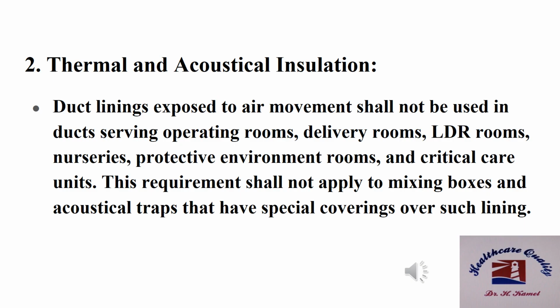Duct linings exposed to air movement shall not be used in ducts serving operating rooms, delivery rooms, LDR rooms, nurseries, protective environment rooms, and critical care units. This requirement shall not apply to mixing boxes and acoustical traps that have special coverings over such linings.